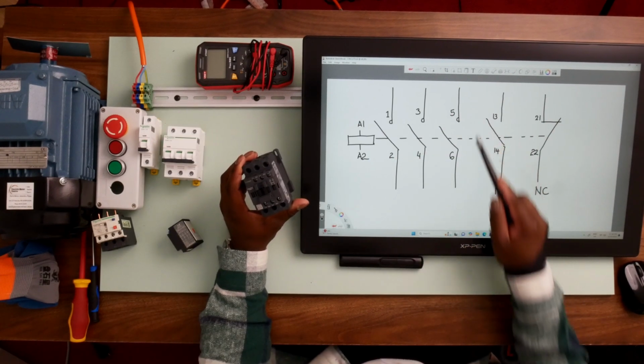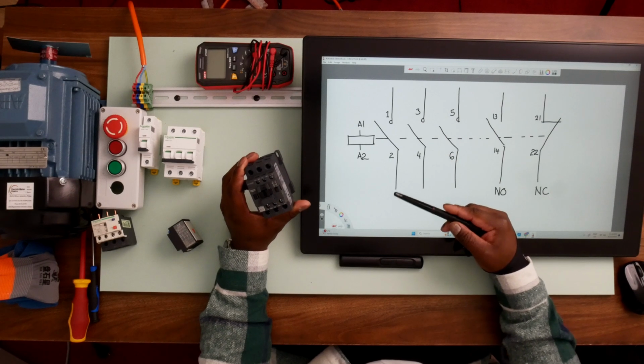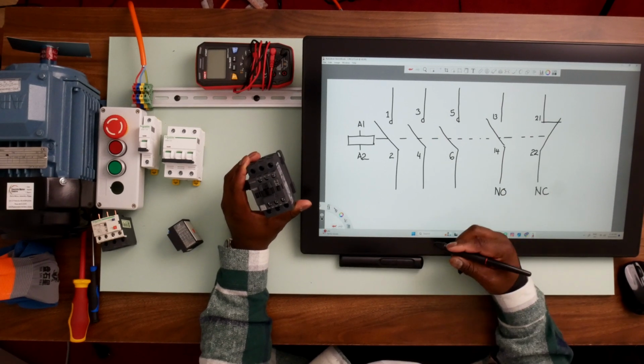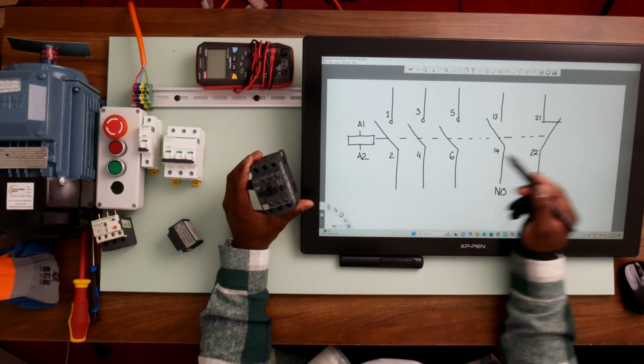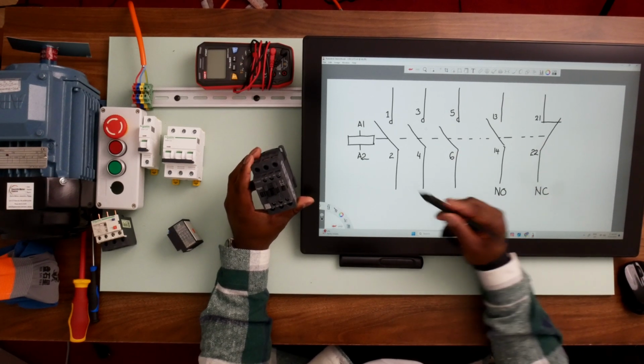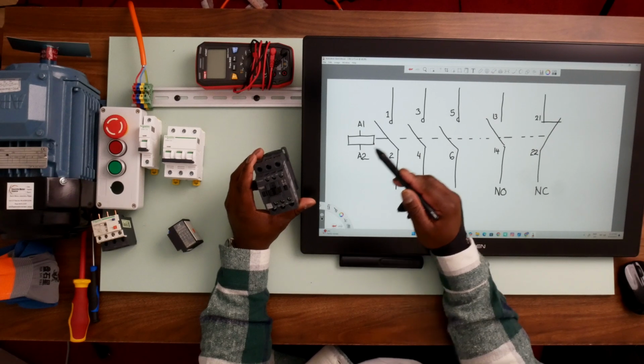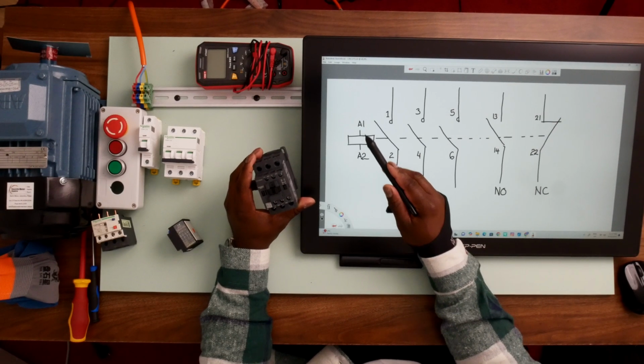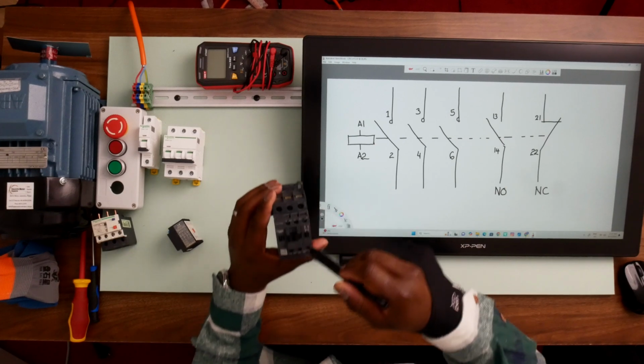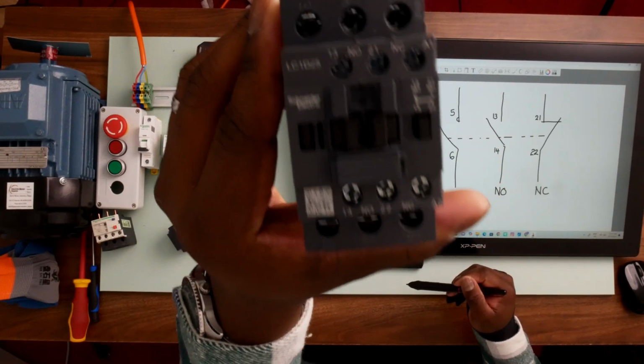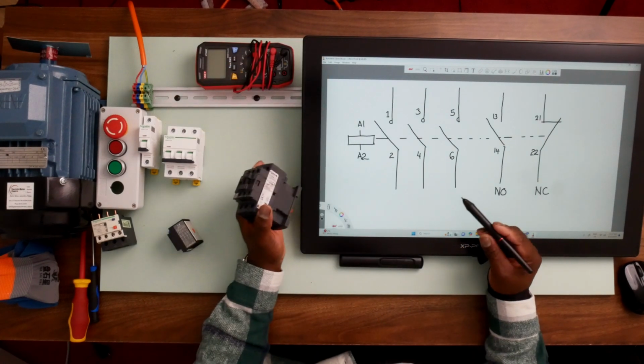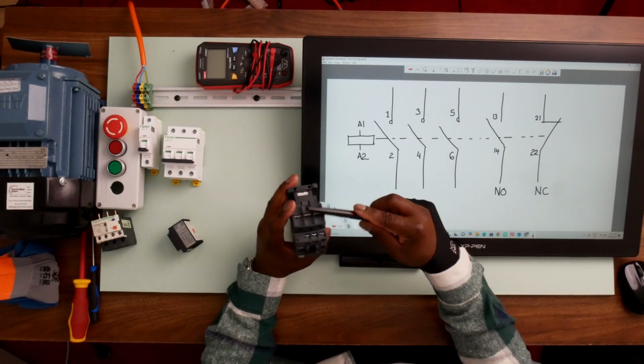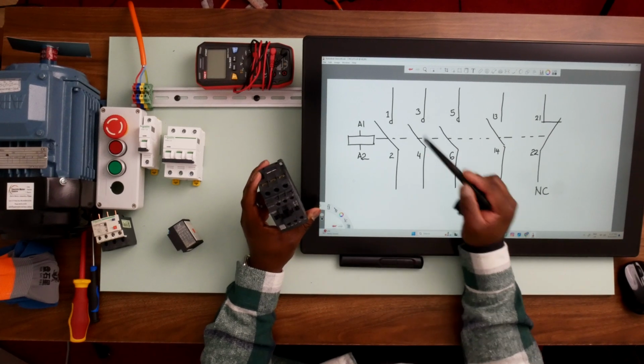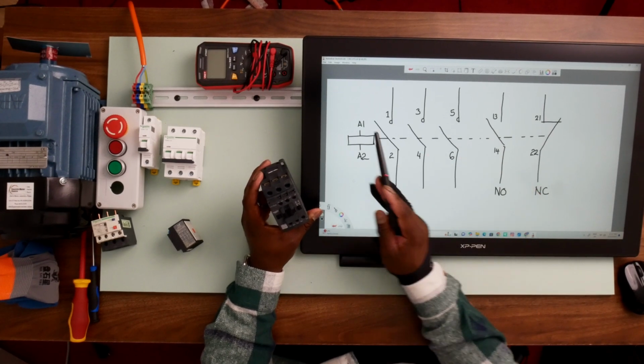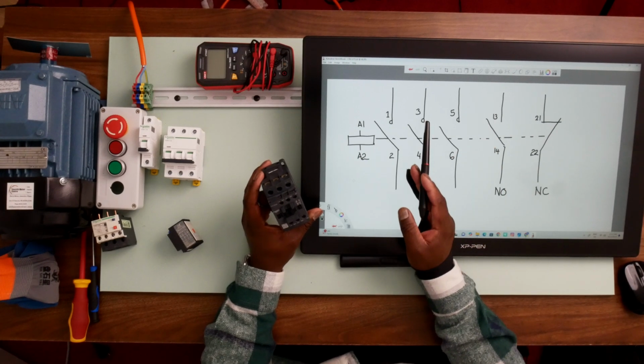This is our contactor. This is the part that belongs to the power circuit. This is the part that switches on our supply to our electric motor windings. The power contacts and the control contacts are all switched on by the contactor coil. So when the electromagnetic coil on the contactor, A1 and A2, is activated, it closes these contacts on the power circuit side of the contactor, which is 1, 2, 3, 4, and 5, and 6. These are the three poles on the power circuit side of the contactor.